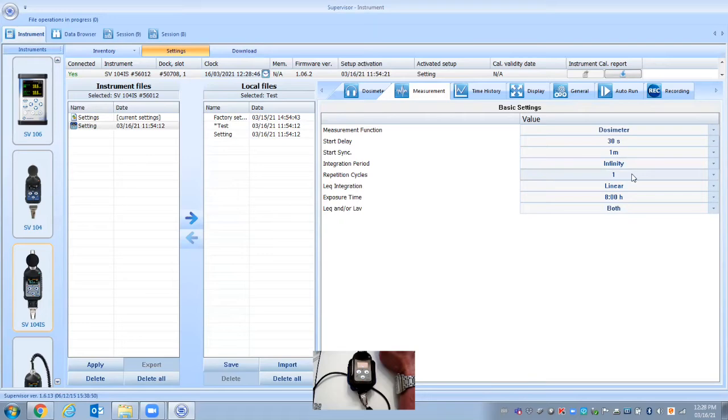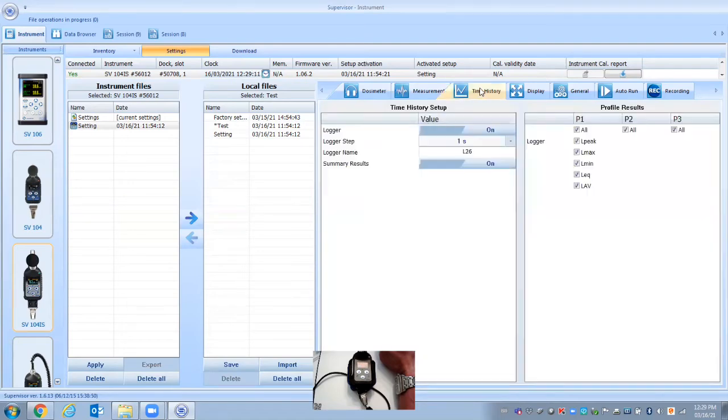The next one down is so we're just going to do basically we're going to turn it on and we're going to do one measurement. There is fancier things you can do. You can set it for a certain amount of time and have it stop and report the exposure time. This is based on an eight hour shift. But if for some reason it was like a 12 hour shift or something like that, you could change that to 12 hours to get exposure over that time. And this would be set to both as well. Time set. So let's go into this next setting here.